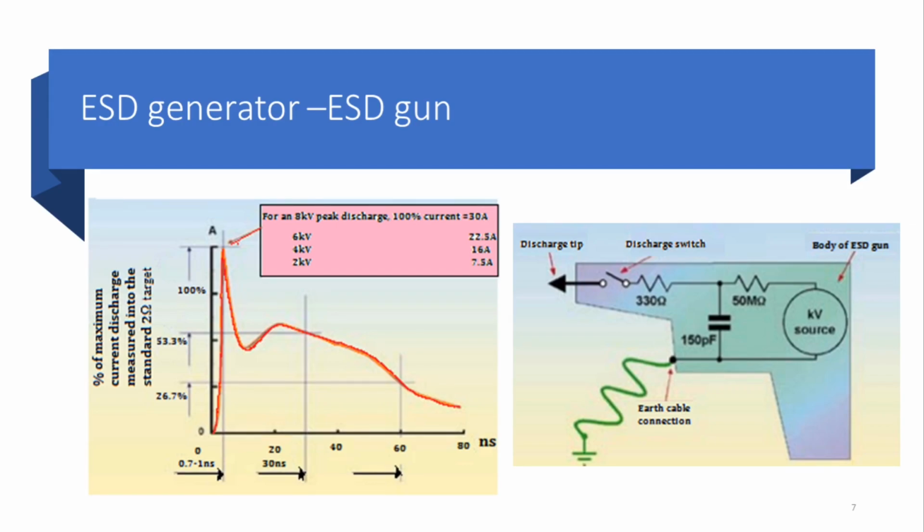So the ESD test aims to simulate the effect of discharges from the fingers of personnel, either directly or via keys or other metal objects held in the hand. The personnel, having been charged to a high voltage by triboelectric charging, usually due to rubbing contacts between their shoes or clothing and dissimilar material used for flooring, storage, etc.